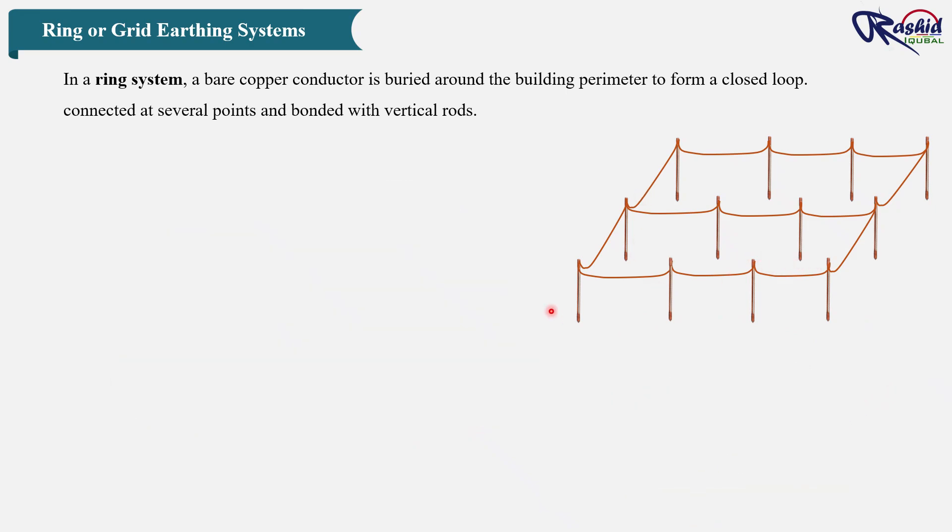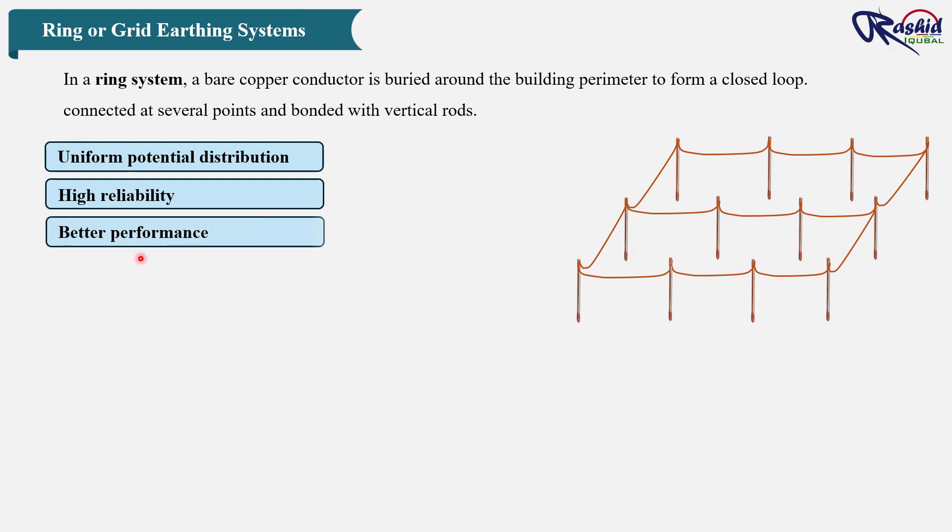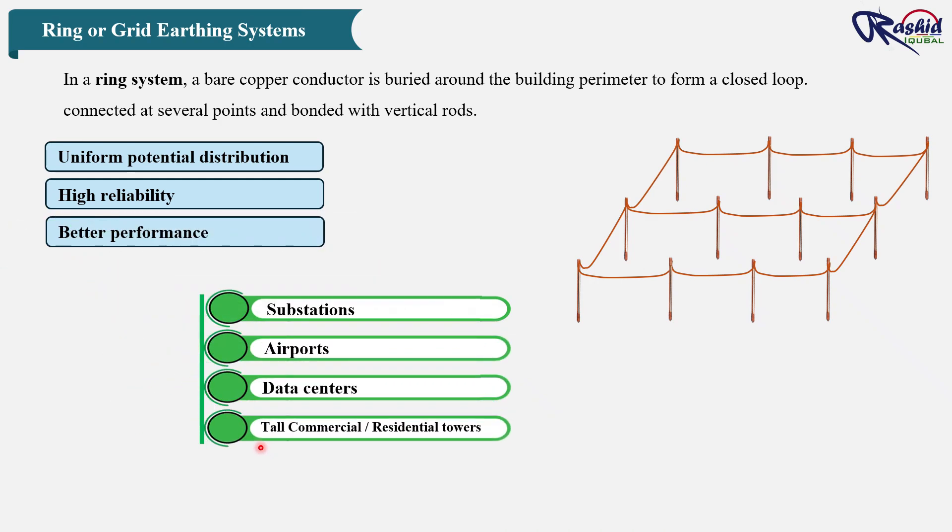This system offers three key benefits: uniform potential distribution, high reliability since multiple parallel paths are available for current flow, and better performance, especially in those areas where soil resistivity is high. That's why ring or grid systems are widely used in substations, airports, data centers, and tall commercial towers where reliability and safety are critical.